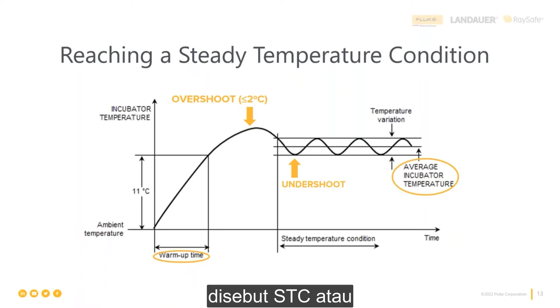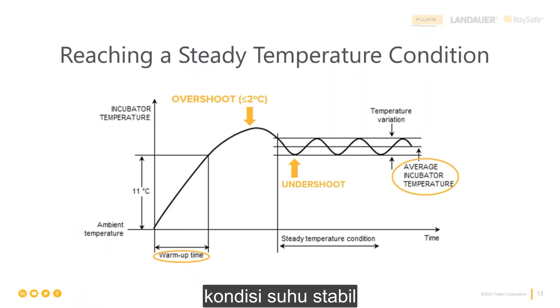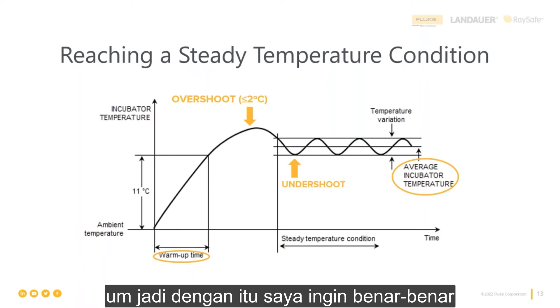So once the incubator has gone through all of these minor temperature oscillations, kind of the picture here, with the temperature varying no more than 1 degree for 1 hour, that's when the incubator reaches that condition that is called STC, or steady temperature condition. So with that, I would like to switch to the next slide and discuss the importance of the concept of STC. Once the incubator achieves STC, its most important function is to keep a uniform environment in all parts of the chamber that Michael was telling us about.